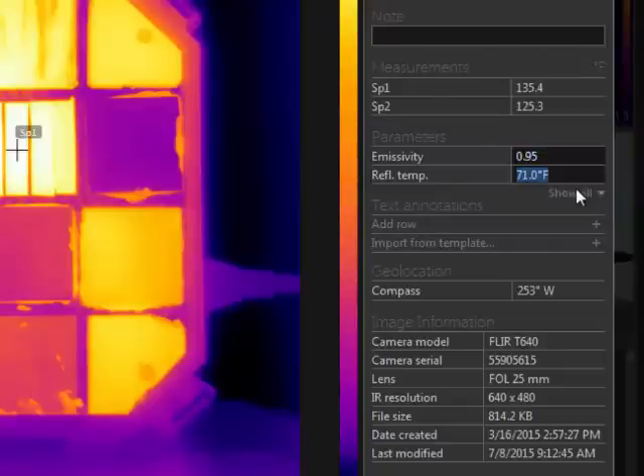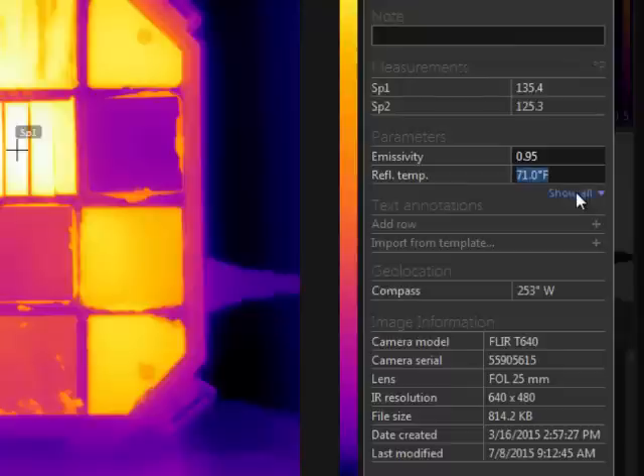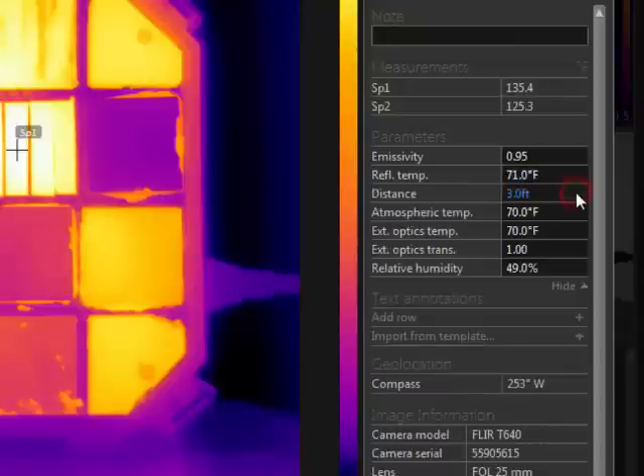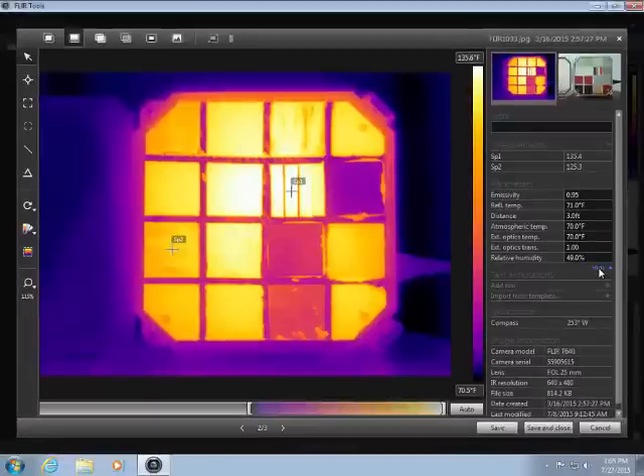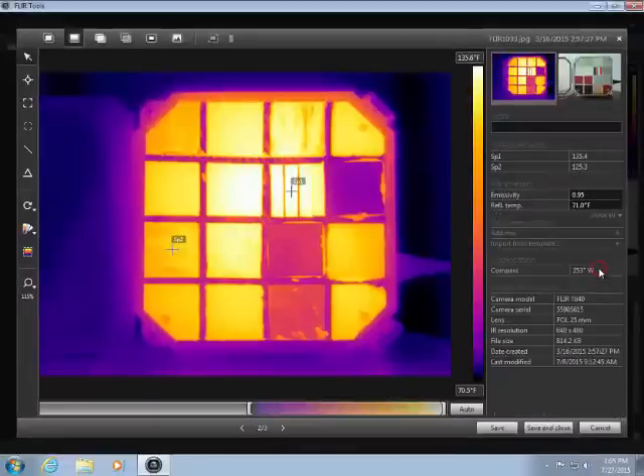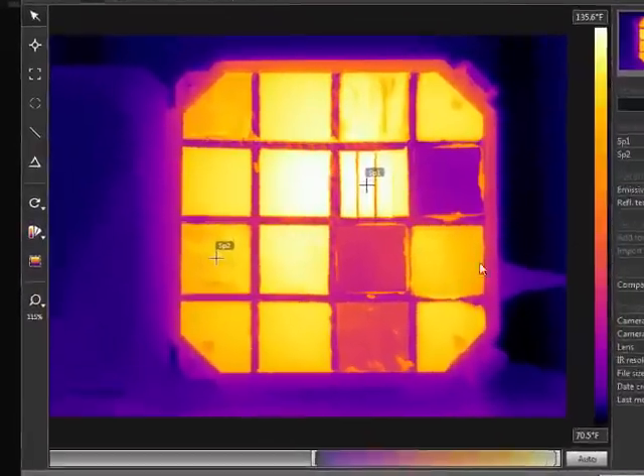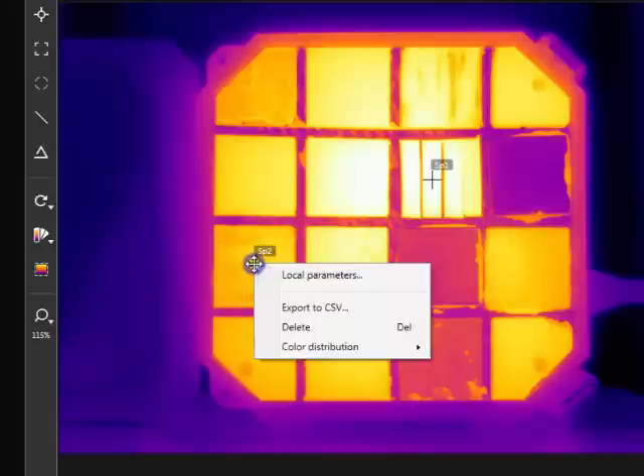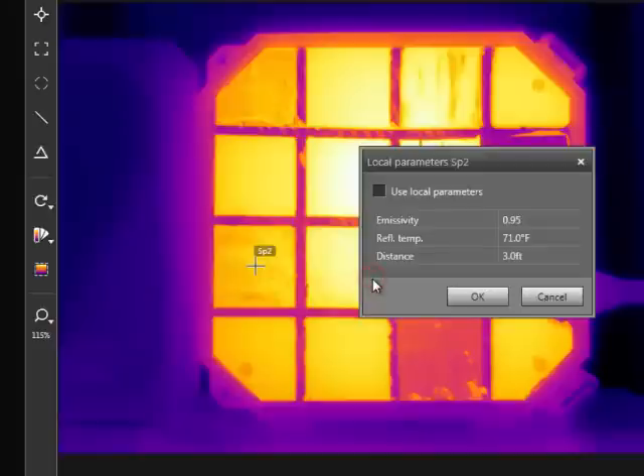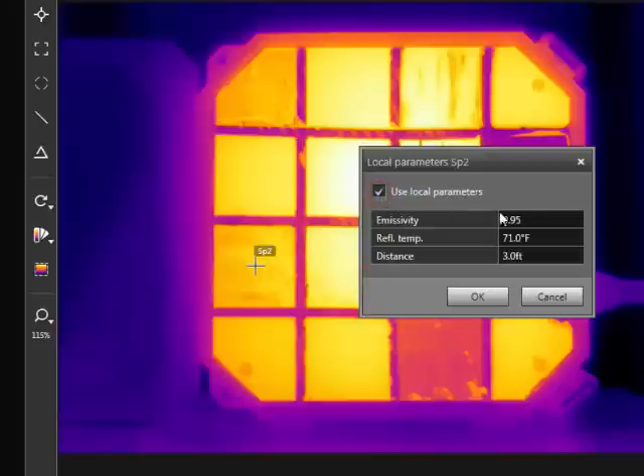Click here to show the atmospheric and external optics parameters. For a complex image, it may be necessary to set local object parameters. You can right-click on any measurement tool and click Local Parameters. This allows you to set a custom emissivity for the material that is being measured.